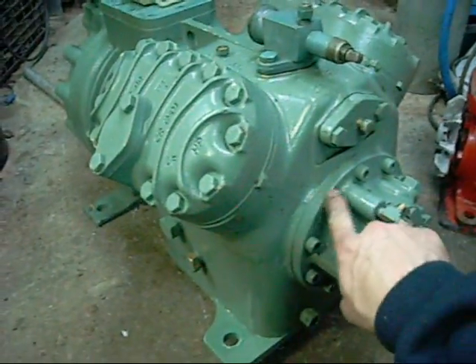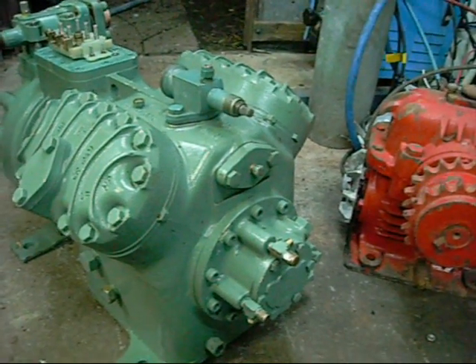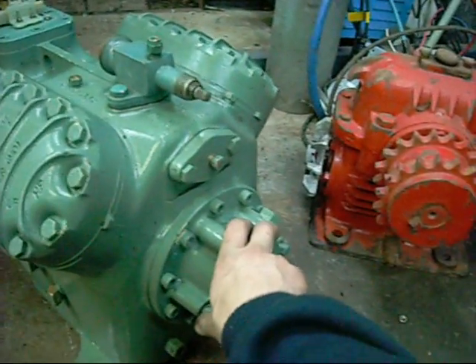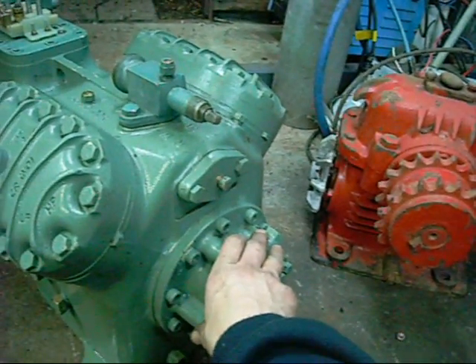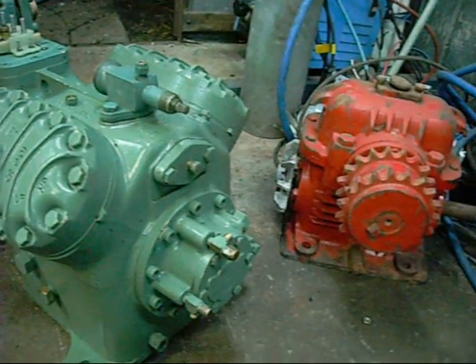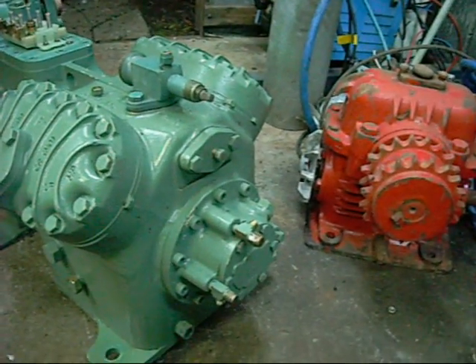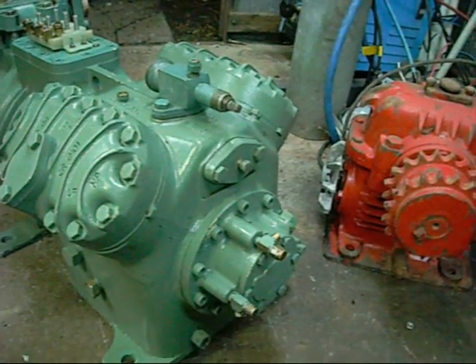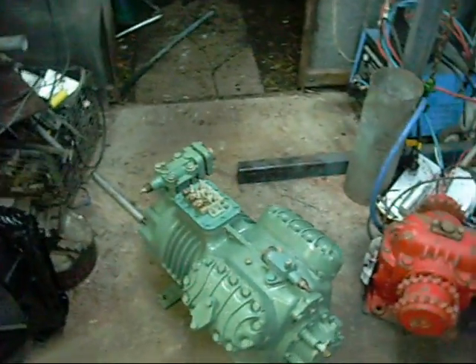That's the oil pump. A YouTuber asked me what it means when their supermarket compressor is throwing up a low oil pressure alert. It basically means this pump's not working properly. So if your system's throwing up a pressure alert like that, shut it down, take the unit offline, and just transfer food to another display case until the system can be repaired. No use running it after the oil alerts come up, because you'll just wreck your compressor. Catch it early.